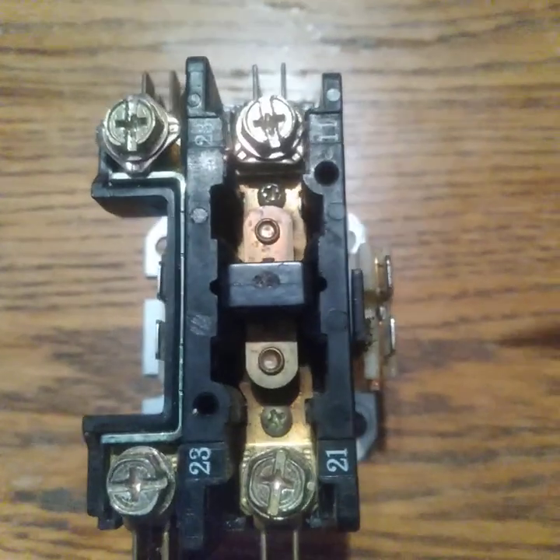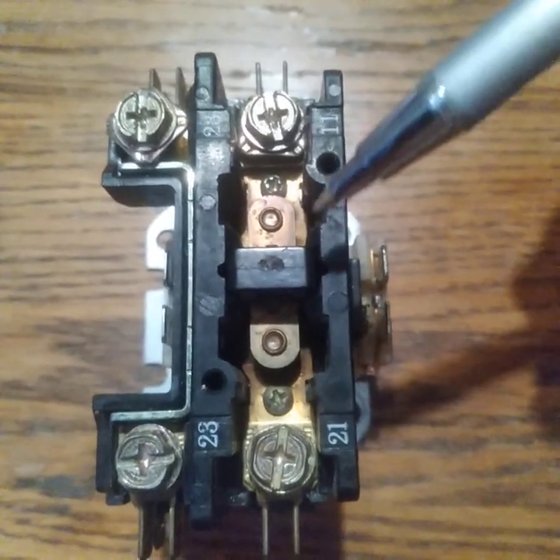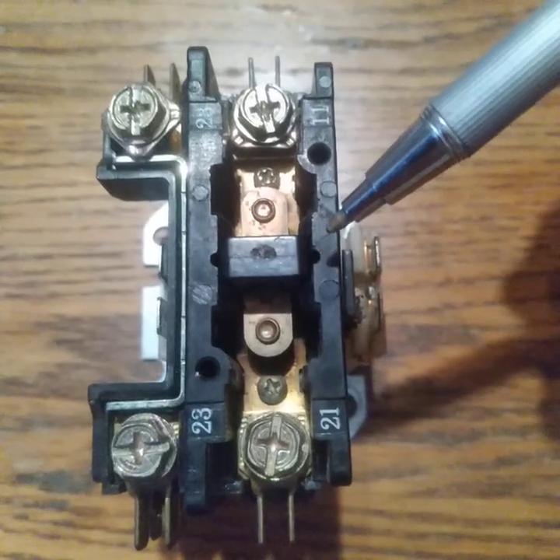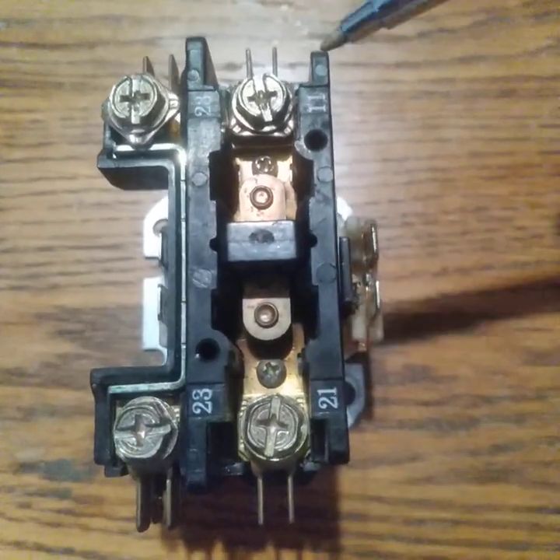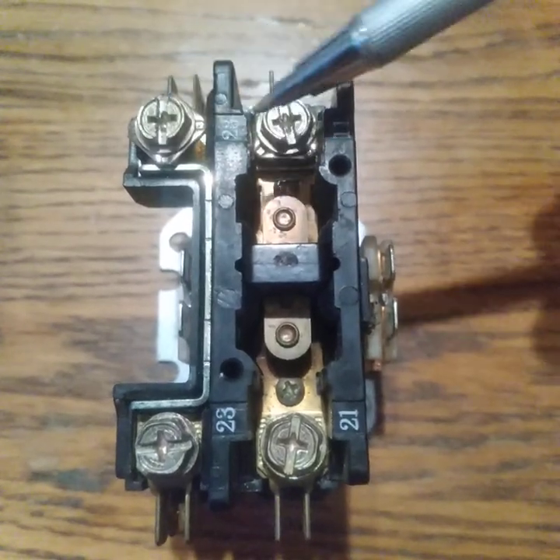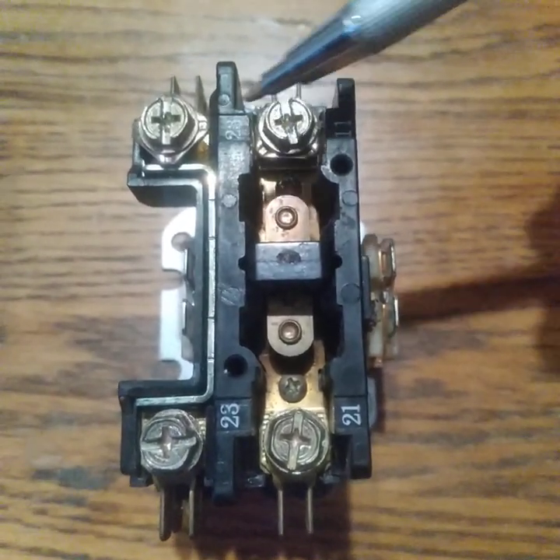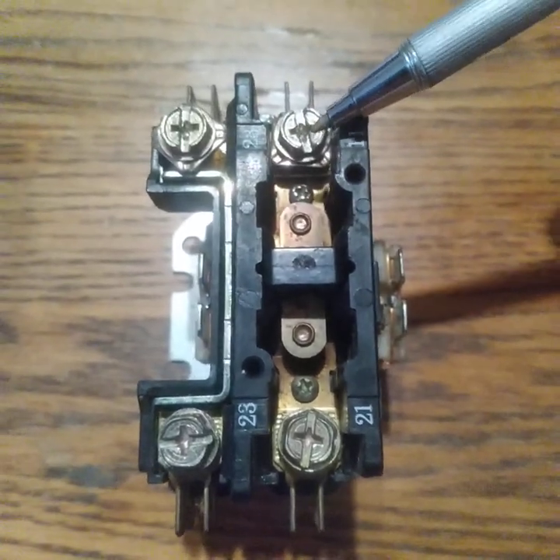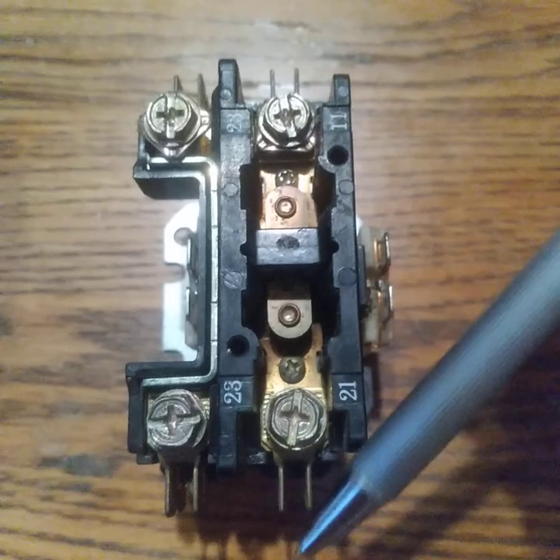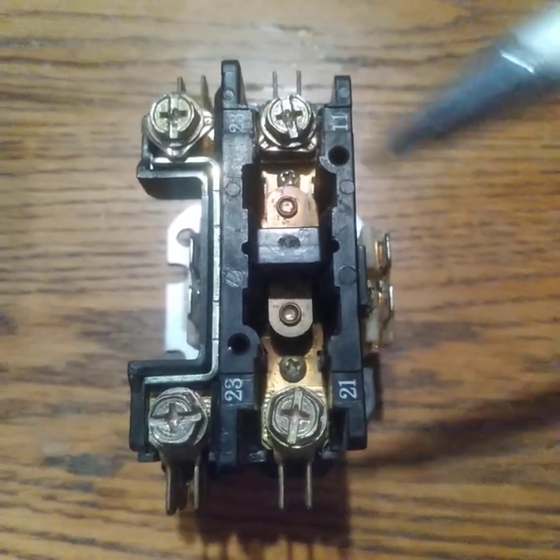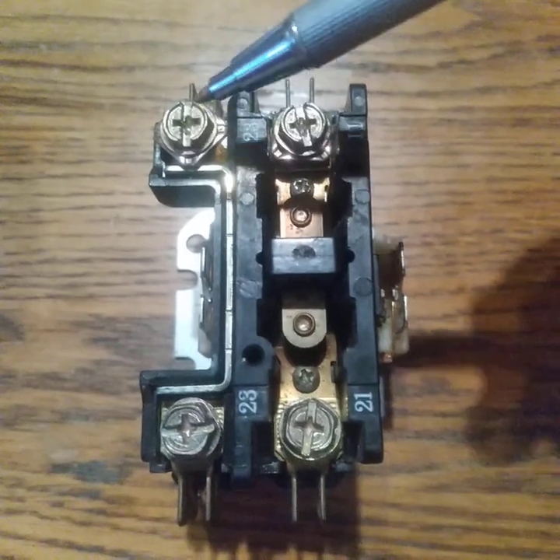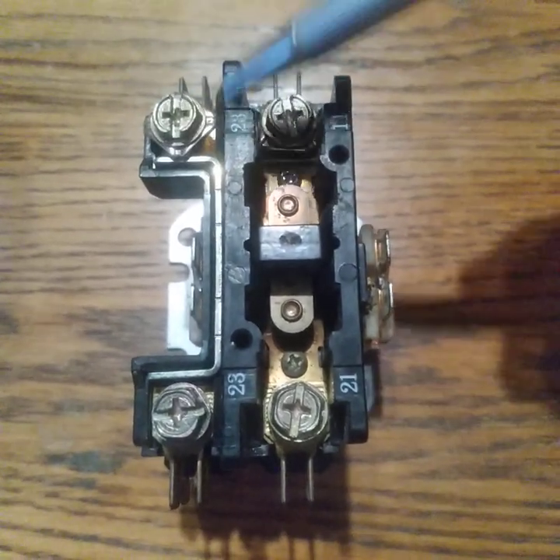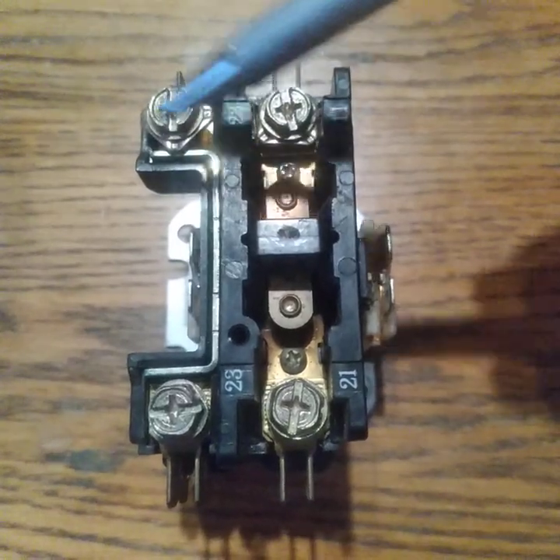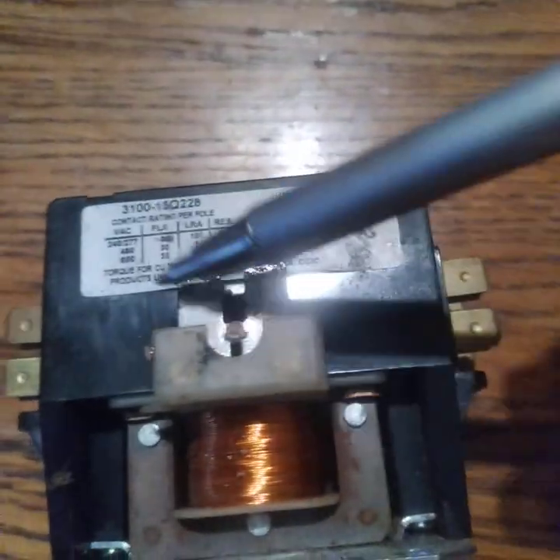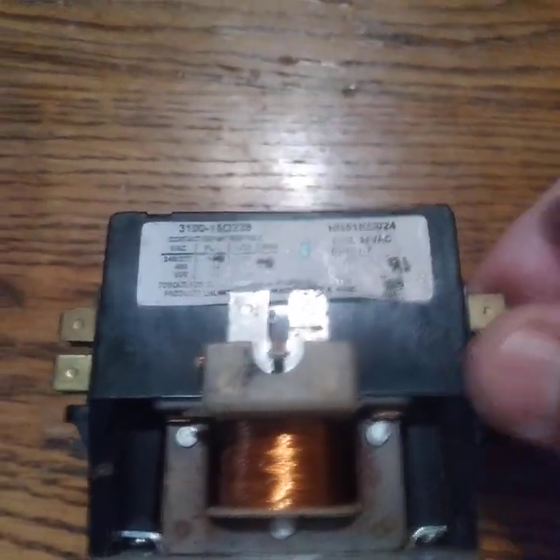One use of this contactor is to take this high voltage here, and if we test the voltage on this terminal and this terminal, T1 and T2, we should have nothing. We should have 0 volts here. We should have voltage here coming from the quick disconnect or the breaker box. If we take one terminal here to ground, we should have 0, one terminal here to ground, cross them over.